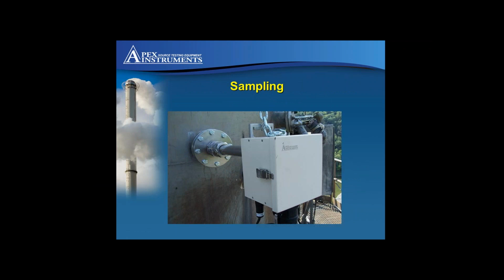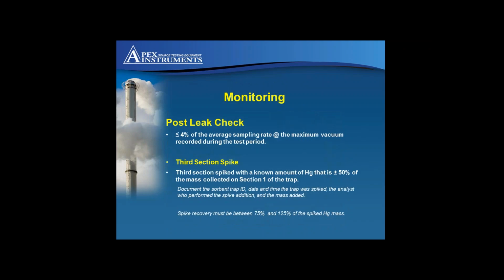A typical view of sampling underway from the source, normally via a 4-inch or 6-inch flange, illustrating the probe into the stack gas and showing the cam-lock quick release technique for inserting and removing the probe. Important for the QC aspect of the sample run that the trap ID is recorded. The system software actually prompts you about 3 times to record the trap identification data into the test file. But as a tester, it is always useful to carry a small notebook and manually record your activities.